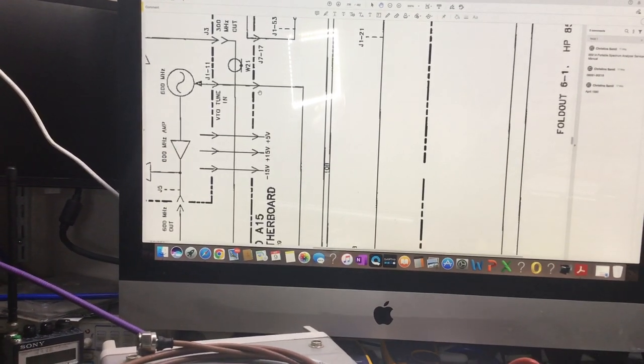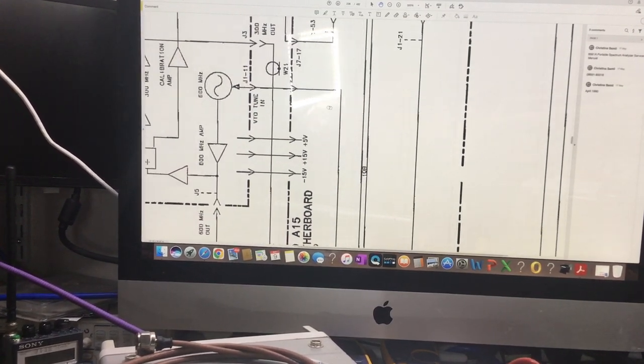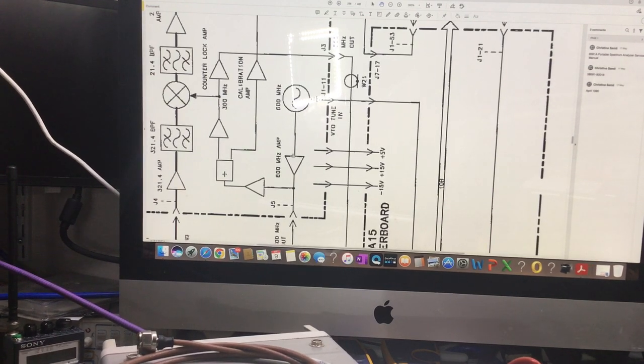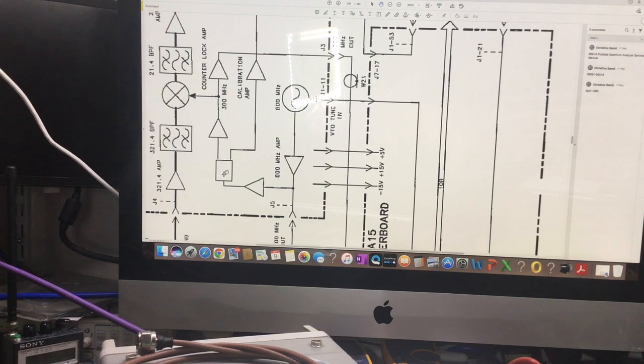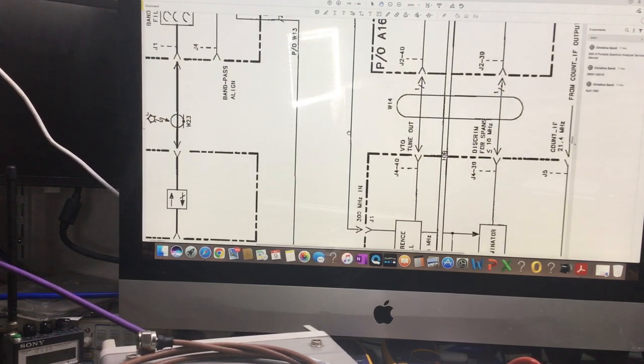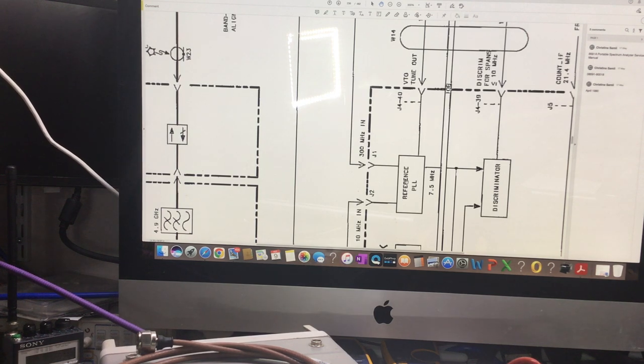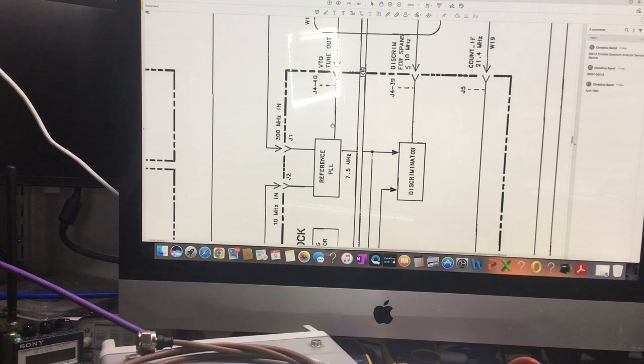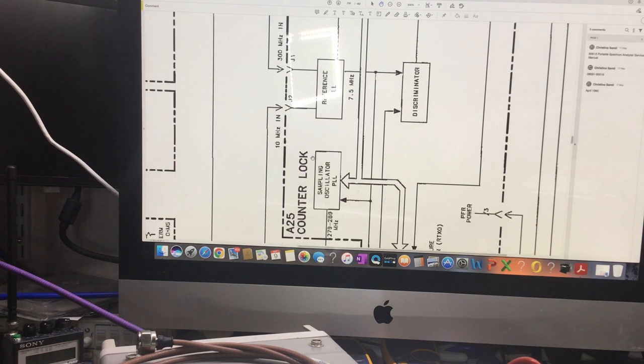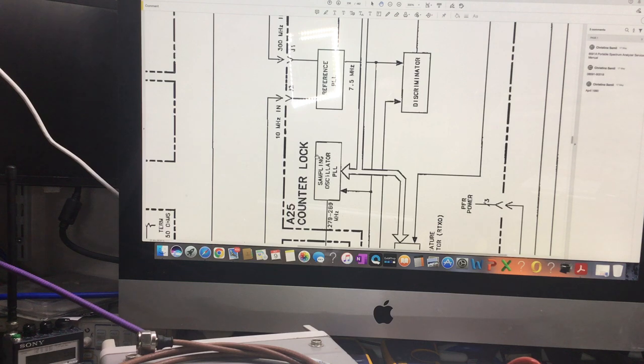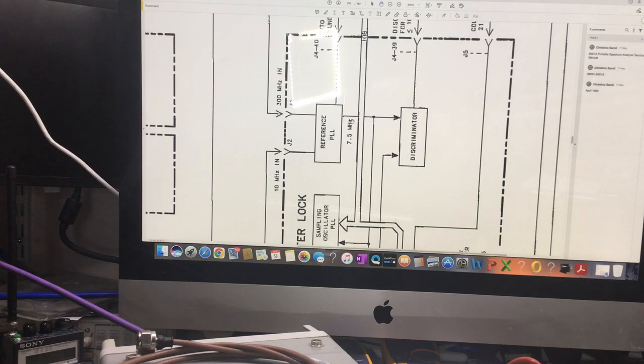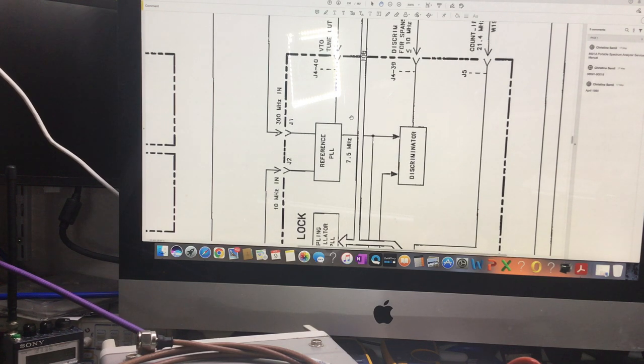It then enters the oscillator within the card that we were looking at earlier, which then obviously controls the output frequency. It gets buffered into a divider by 2, so we get a 300 megahertz output, which then feeds this mixer and then comes back out on that coaxial cable, right the way back, and gets fed into the reference phase lock loop. So because we're on this line here and we can't see any pulses, any steady DC voltage, I think we've reached the prognosis that the reference PLL in the frequency counter module, the counter block, has failed. And unfortunately it looks as if that's the case.